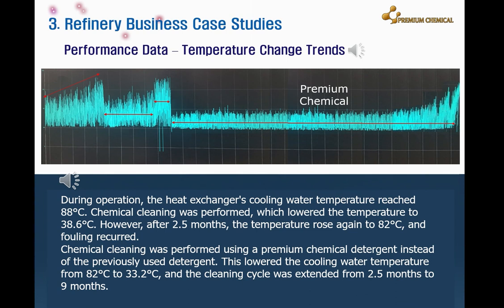Now, let's explore performance data after chemical cleaning with premium chemicals. Performance data is a formal verification process for cleaning quality through quantitative data. Quantitative data can be verified through 3 factors: temperature changes, flow rate changes, and visual inspection. The graph displayed on the screen is excellent data provided by the customer, representing real-time temperature measurements in the monitoring room.